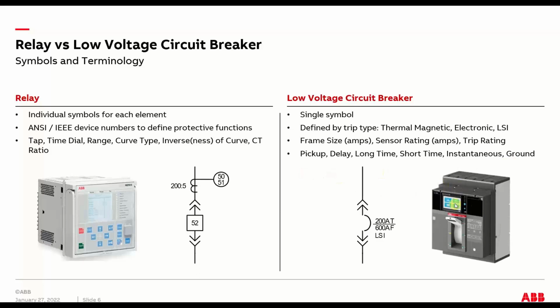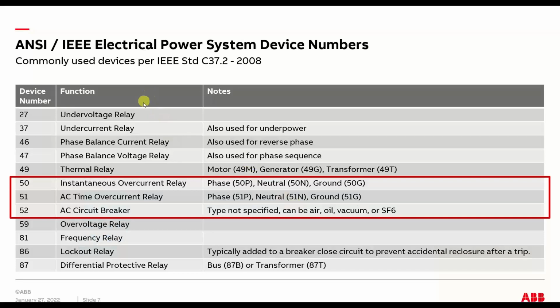The CTs in a breaker like this are called sensors. So completely different vocabulary, but both describing exactly the same physical phenomenon and basic kind of components. Here's just a breakdown of the device numbers, the ANSI IEEE standard device numbers. And these are not only valid for the circuit breaker, switchgear world, but also control.